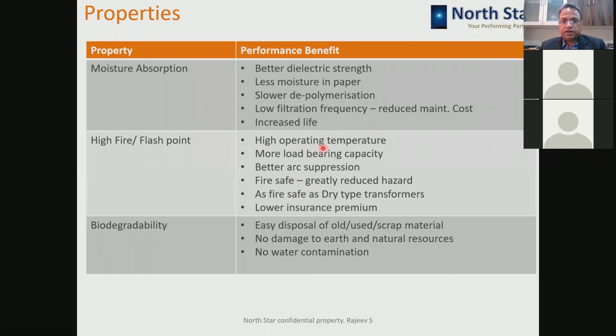Since they are fire safe, there is very little hazard of accidents, fire accidents, and loss of property. So because of this, they are as safe as any dry type transformer. So wherever you are using a dry type transformer, there you can use oil filled transformers. Mineral oil filled transformers you can replace by doing retrofilling with natural and synthetic ester. So you don't have to always go for dry type transformers, which are costlier than oil filled transformers. So with some marginal increase in the price, you can use synthetic and natural ester in the oil filled transformers.